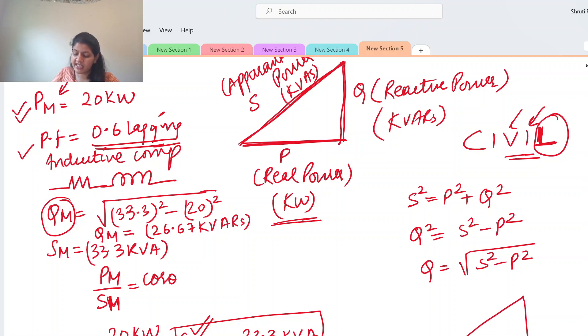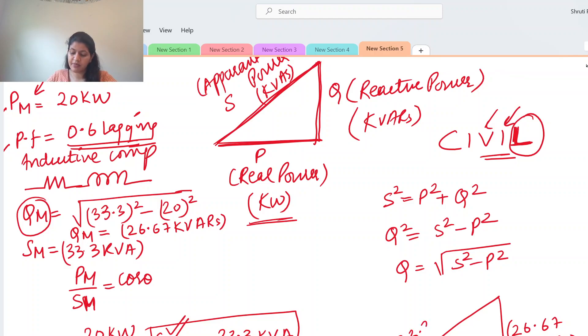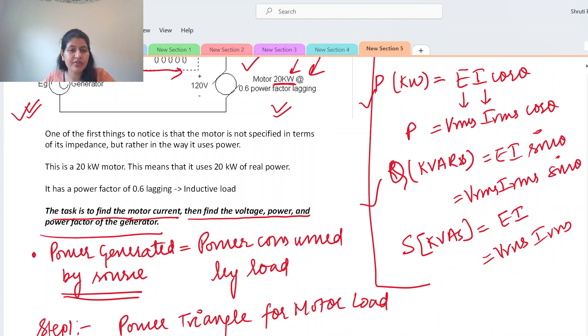Drawing the power triangle for the motor: P = 20 kW, Q = 26.67 kVARs (positive because it is an inductive load), and apparent power S = 33.3 kVA.